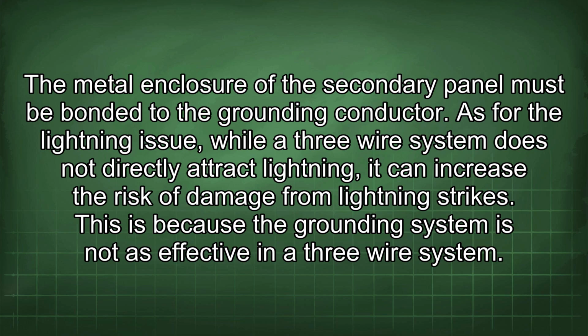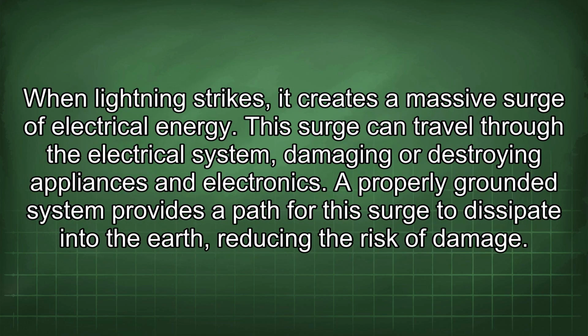As for the lightning issue, while a 3-wire system does not directly attract lightning, it can increase the risk of damage from lightning strikes. This is because the grounding system is not as effective in a 3-wire system. When lightning strikes, it creates a massive surge of electrical energy. This surge can travel through the electrical system, damaging or destroying appliances and electronics. A properly grounded system provides a path for this surge to dissipate into the earth, reducing the risk of damage.